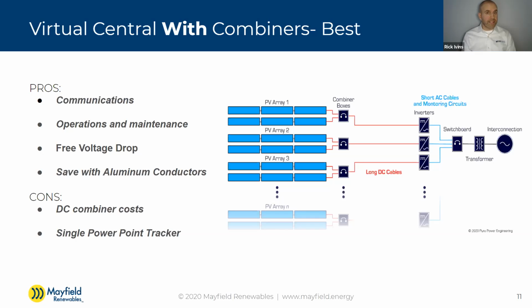And aluminum is a softer metal, so if you keep retorquing, that problem would be worse than with copper. So I wouldn't necessarily say the issue is copper versus aluminum as much as that practice in O&M might need to change. Torque it once and don't torque it again unless the thermal imaging shows that it's an issue. Mm-hmm.